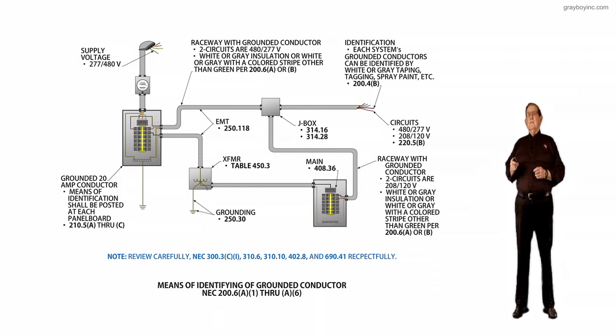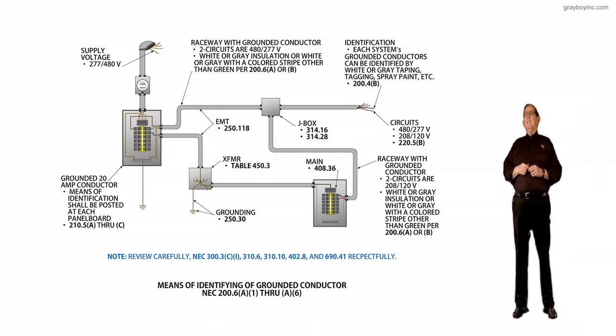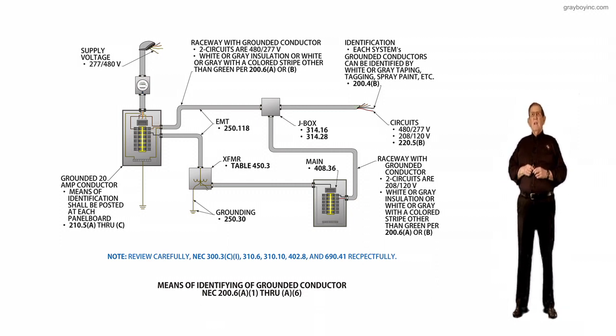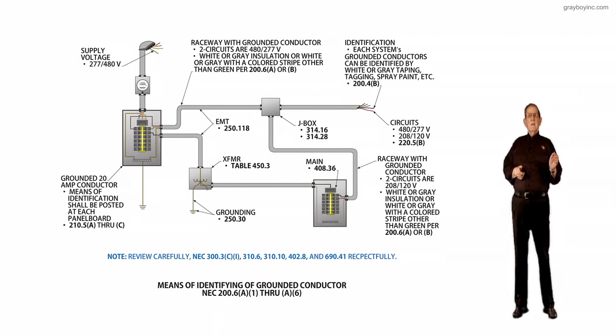Fourthly, I'd like to look at the title head and information next to the one I just discussed, and identification in the first bullet says each system's grounded conductors can be identified by white or gray taping, tagging, spray paint, and so forth. Now, fifthly, let's look at the panel board at the service equipment, and it's the illustration down toward the bottom of the panel board.